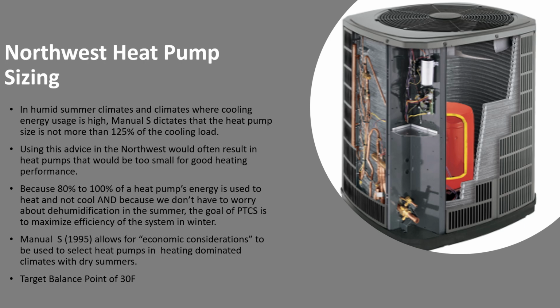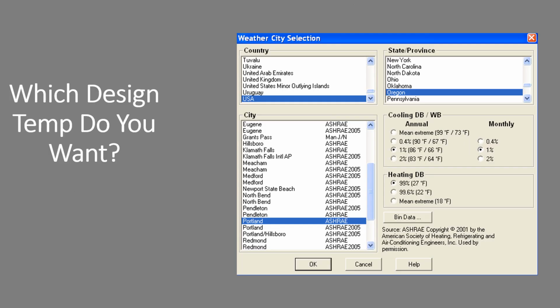If you're really into reading ACCA manuals, Manual S says, boy, if you don't live in a humid place and you're in a heating dominated climate, you can use economic considerations. And there's been a lot of research done in the Northwest to prove that those economic considerations point to a target balance point of 30 degrees Fahrenheit.